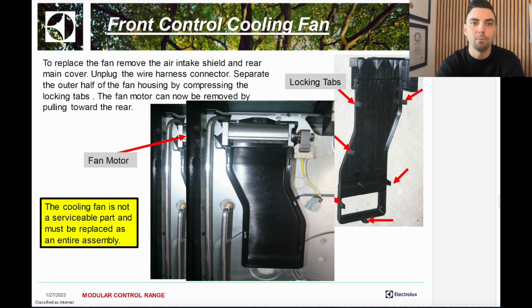To replace the fan, remove the air intake shield and remove the main cover. Unplug the wire harness connectors. Separate the outer half of the fan housing by compressing the locking tabs. And the fan motor can now be removed by pulling toward the rear. So the cooling fan is not a serviceable part and must be replaced as an entire assembly as well.